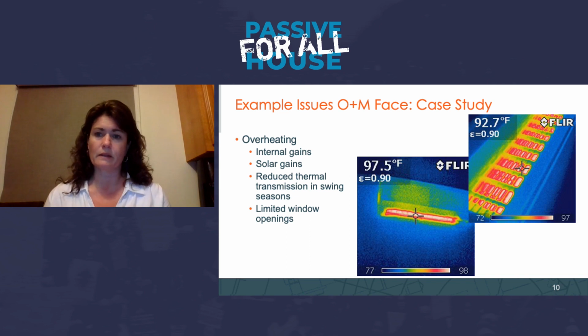So there are other issues. This is just one mechanical issue that causes overheating in passive houses. We have very high internal gains per square foot in our multifamily buildings, even compared to solar gains. So usually we're looking at 2 to 1 or 3 to 1 times the gains, internal gains versus solar gains. So we're internally dominated by gains, not from solar. We do have solar, right, which then compounds it depending on which side of the building you're on.